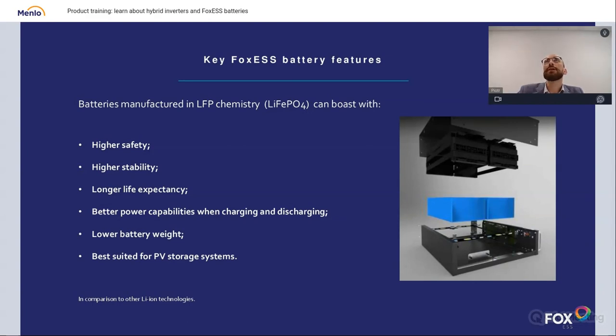So yeah, they just work. They don't heat up. They are stable. Of course, if you short the terminals of the whole stack, that may cause fire because there is a very, very large amount of energy stored in the system and it can be outputted in an instant. So the cables may burst in this case, but those batteries will live. The chemistry won't be changed. They will output a very large amount of energy instantly, but they are designed to do that every day. So yeah, I really don't have any replacements for those batteries because they just work.